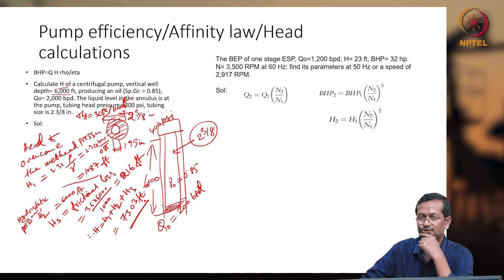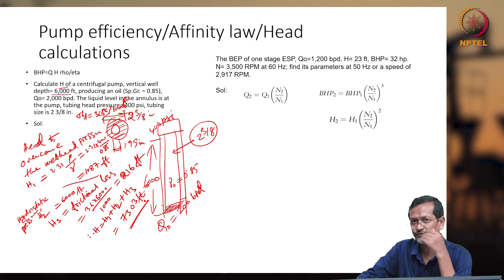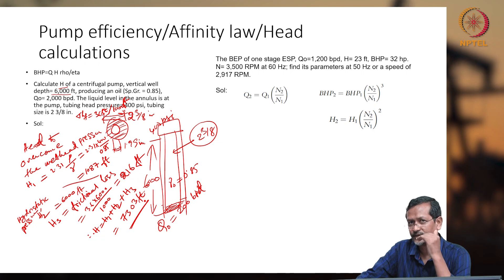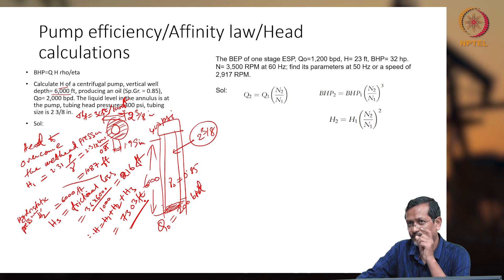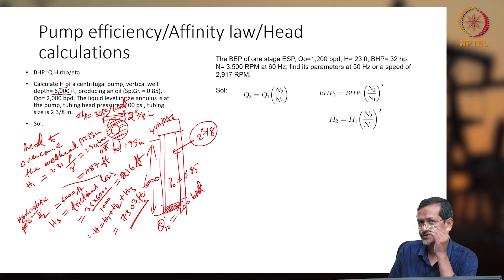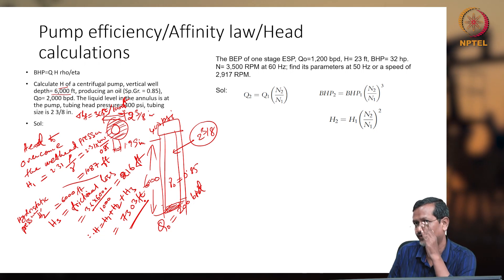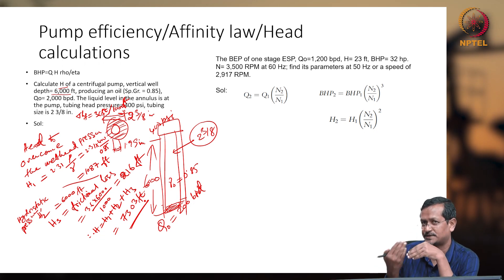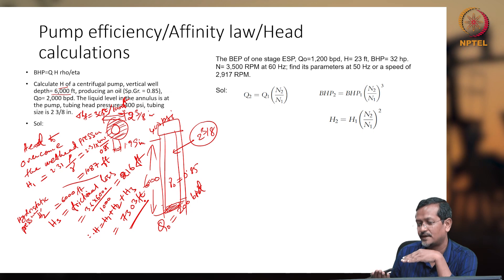Now you have seen the formulation for the affinity law. The affinity law states: flow rate Q is proportional to N, BHP is proportional to N cubed, and H is proportional to N squared. If you change speed from 60 Hz to 50 Hz or vice versa, you can get the new flow rate, BHP requirement, and head requirement approximately from this formula.